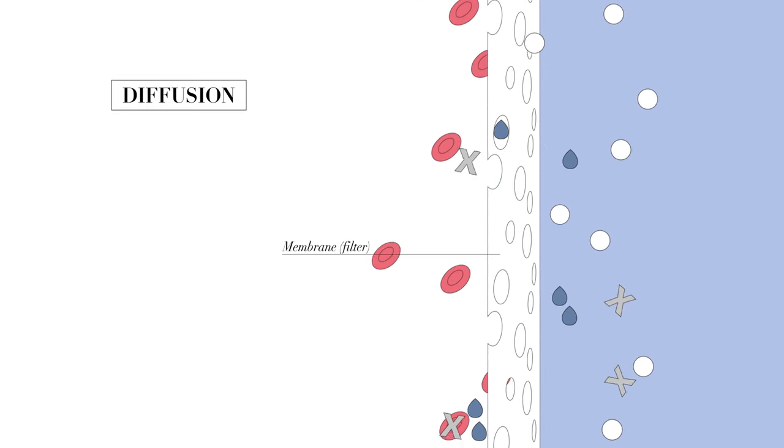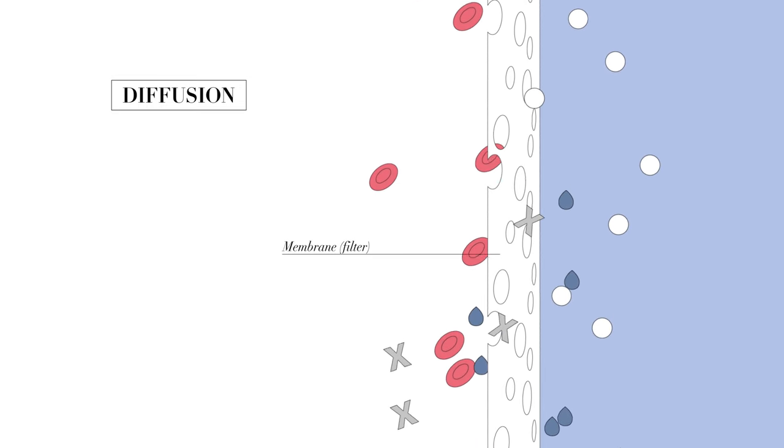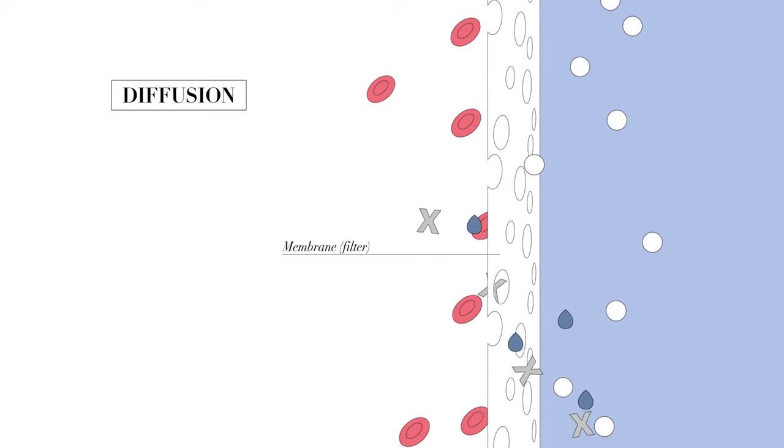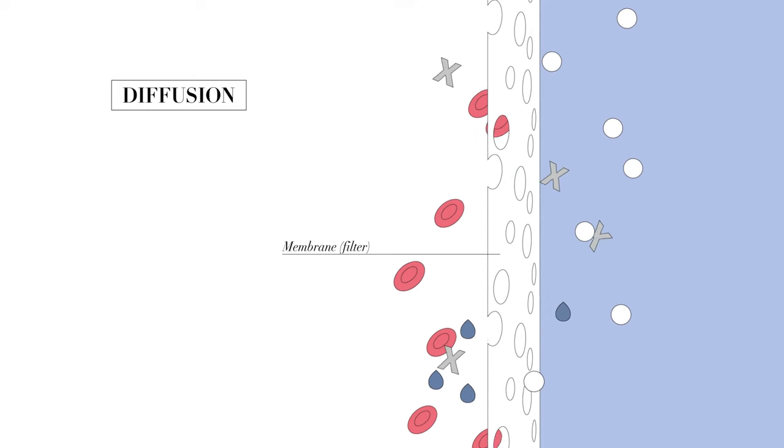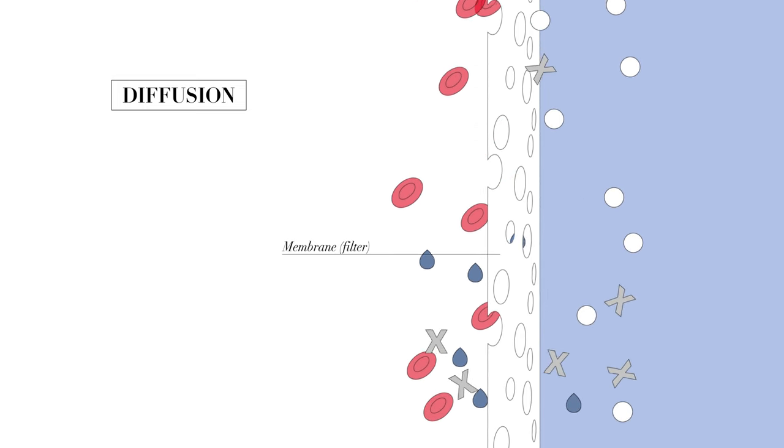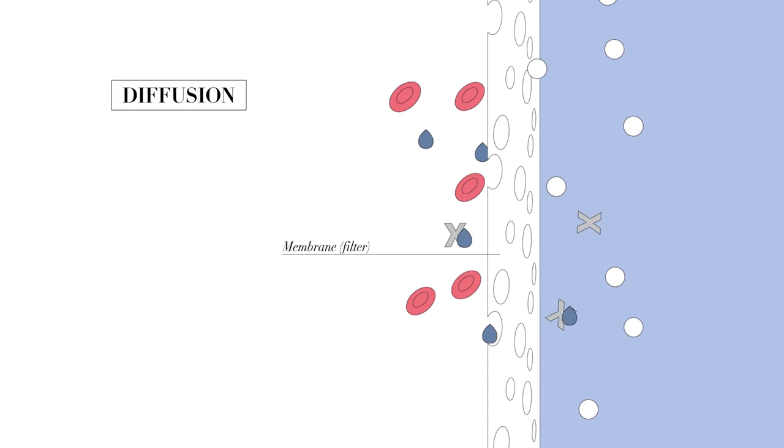Metabolic toxins, urea, and other small particles pass through the membrane of the hollow fibers and are thus filtered out of the blood. By contrast, vital substances and blood cells are held back due to the small size of the pores.